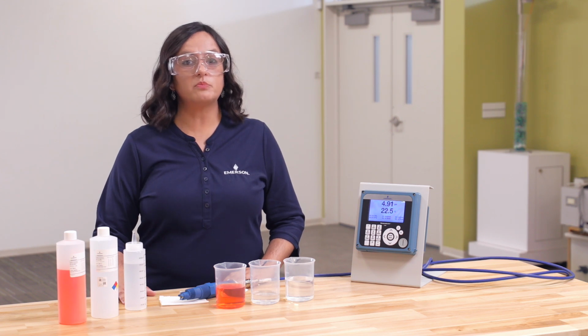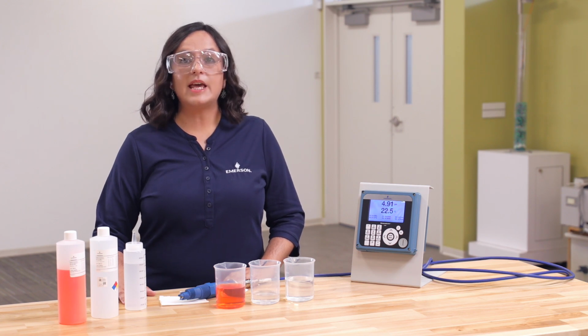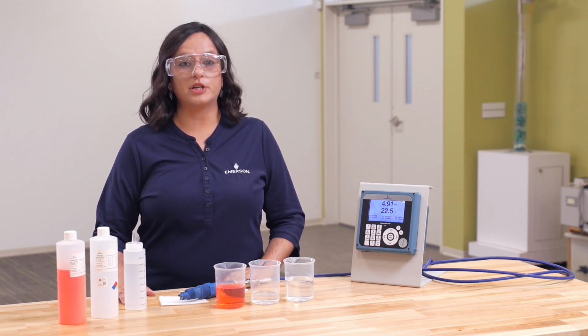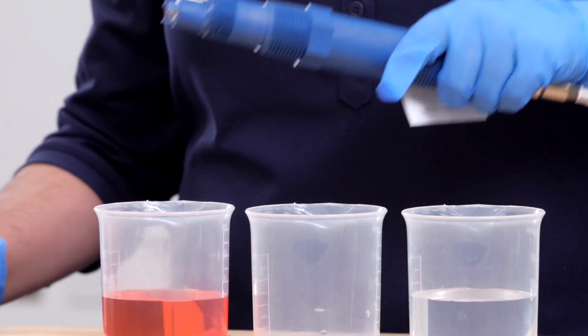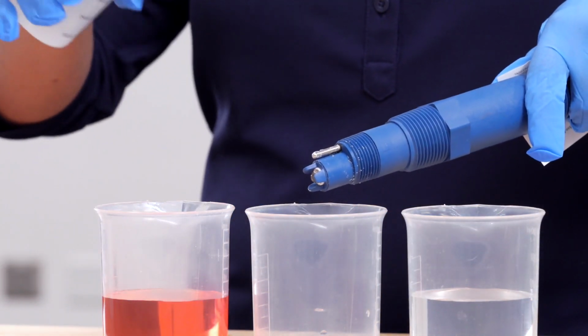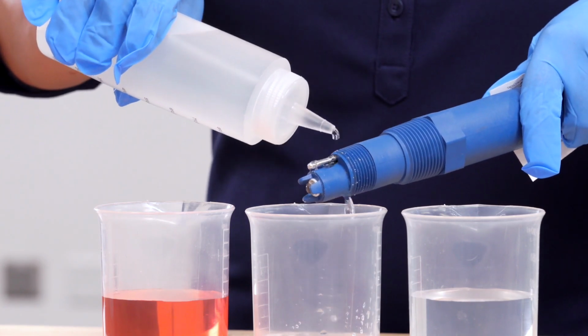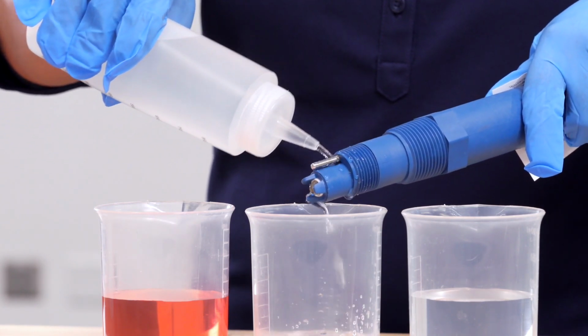There are two ways to perform a pH calibration, auto and manual. Today we will be going through the auto calibration. First, ensure that the pH sensor is clean by rinsing the sensor with tap water to remove any process liquid and debris.